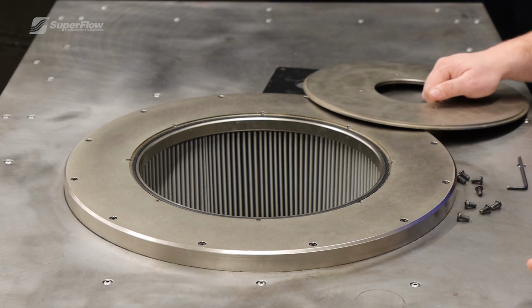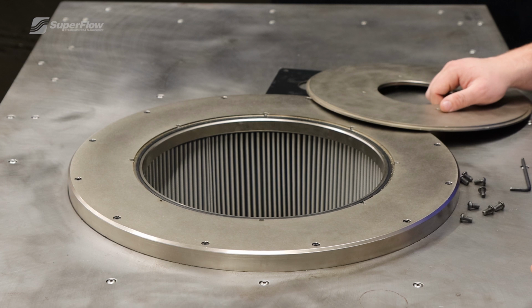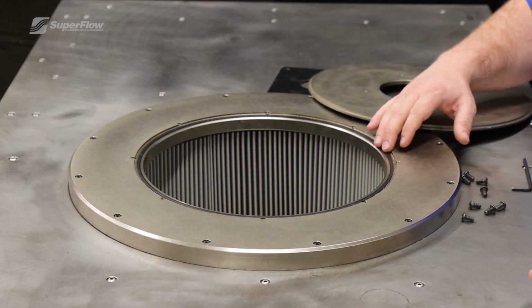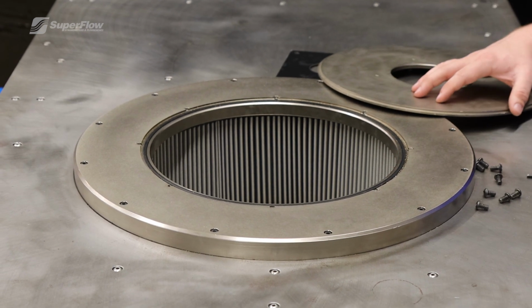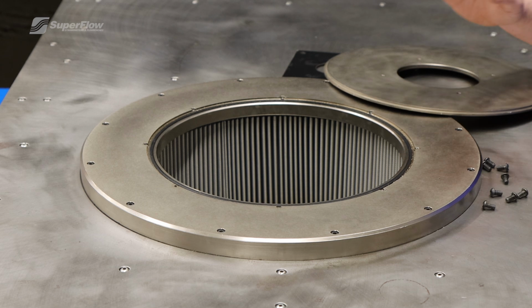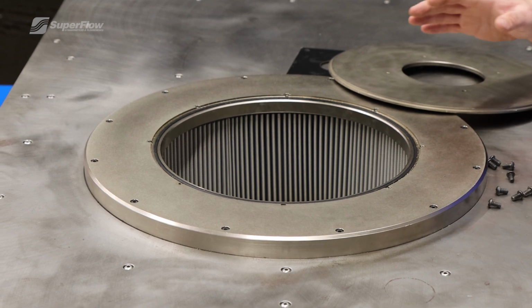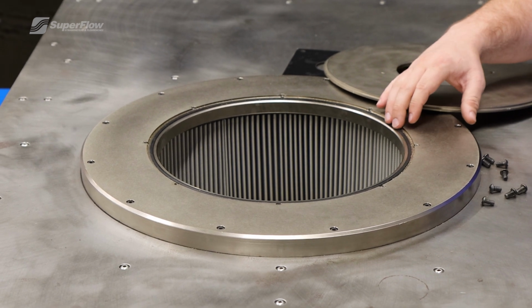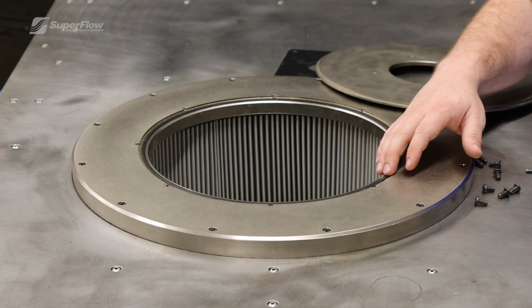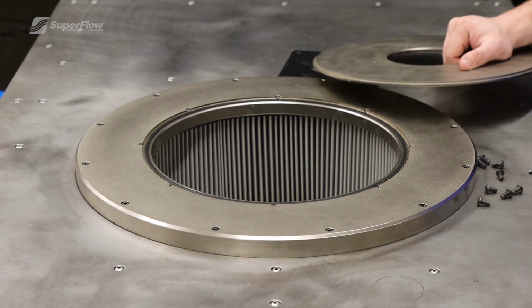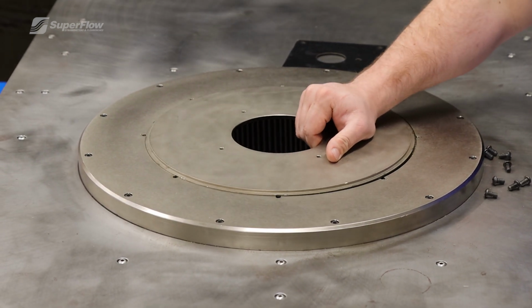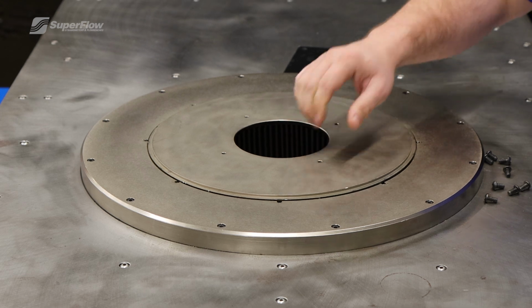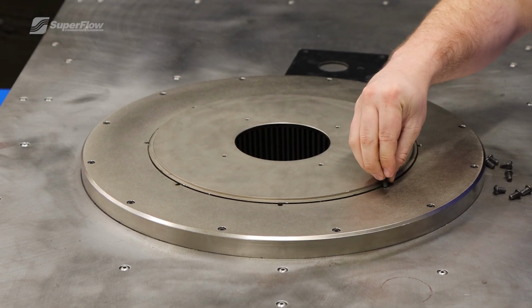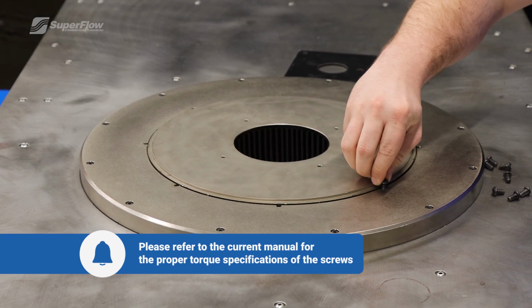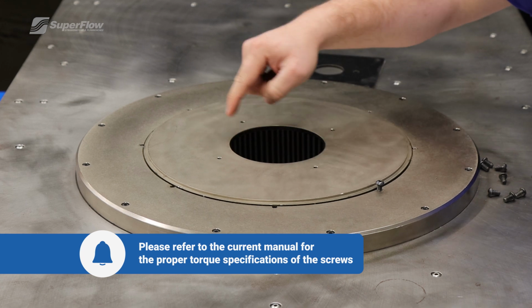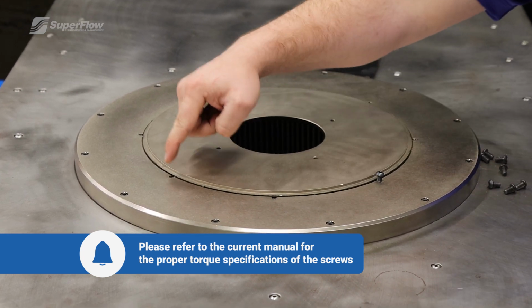Properly reseal the top cover plate. You will make sure both the gasket and the bottom of the cover plate are free of any debris and imperfections, and then apply a light coat of vacuum grease to the O-ring here. And as you put the cover back on, you'll put all 8 screws back in, and you'll tighten them down in a crisscross pattern for a nice even seal.